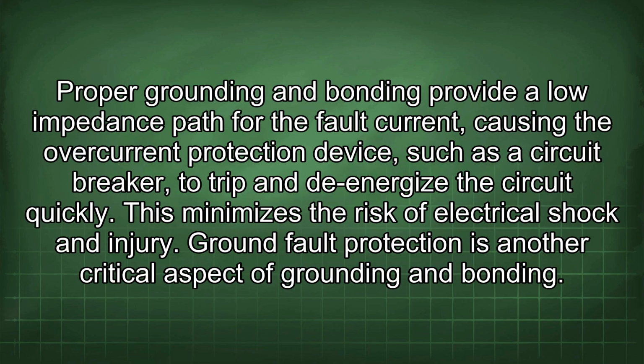Proper grounding and bonding provide a low impedance path for the fault current, causing the overcurrent protection device, such as a circuit breaker, to trip and de-energize the circuit quickly. This minimizes the risk of electrical shock and injury. Ground fault protection is another critical aspect of grounding and bonding.